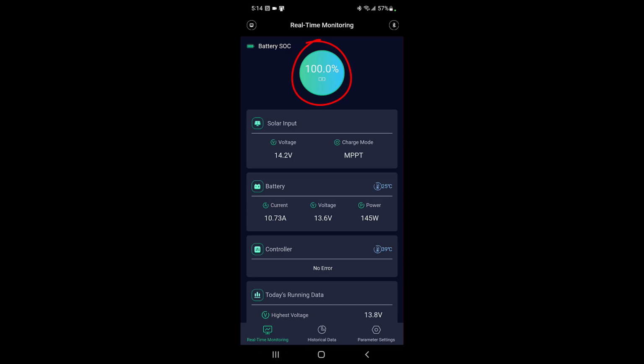You have to take this with a grain of salt, because it's really calibrated more for lead acid batteries and not so much for lithium ion or lithium iron phosphate. There doesn't appear to be a way to recalibrate this state of charge percentage for those lithium chemistries, so you kind of have to rely on battery voltage to determine your actual state of charge.